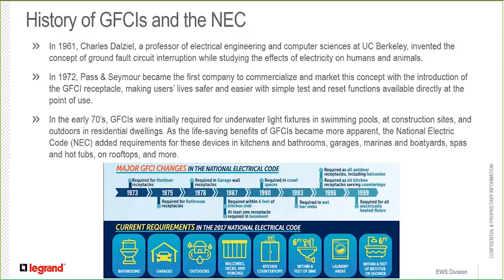In the early 1970s, GFCIs were initially required for underwater light fixtures in swimming pools. As the life-saving benefits of GFCIs became more apparent, the National Electric Code added requirements for these devices in kitchens, bathrooms, garages, marinas and boatyards, spas and hot tubs, on rooftops, and more. You can see in the chart at the bottom of this page how the requirements for GFCIs in the home have proliferated over the years, starting with outdoor receptacles in 1973, moving on to bathrooms in 1975, garages in 1978, and then on down the line to where we are today, which is GFCIs are required in bathrooms, garages, all outdoor receptacles, balconies, decks and porches, kitchen countertops, within 6 feet of any household sink, laundry areas, and within 6 feet of any bathtub or shower.